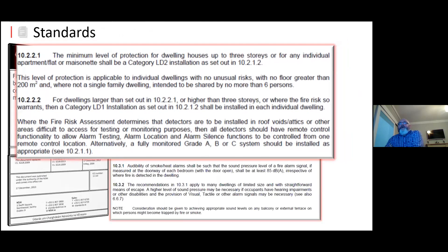Looking at 10.2.2.1 — the minimum level of protection for a house up to three stories, or for individual apartments, flats, or maisonettes, is LD2. This level of protection is applicable to individual dwellings with no unusual risk, with no floor area greater than 200 square meters, and not a single family dwelling intended to be shared by more than six persons. For dwellings larger than 10.2.2.1 or higher than three stories, a fire risk assessment would have to be done and a category LD1 installation may be required.